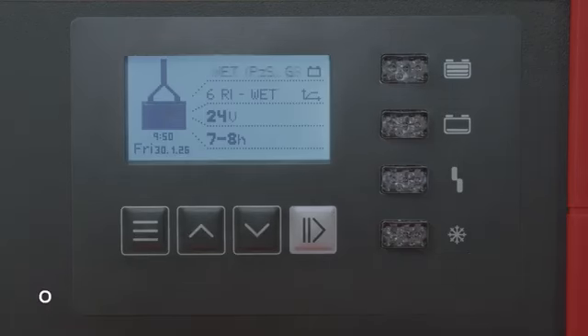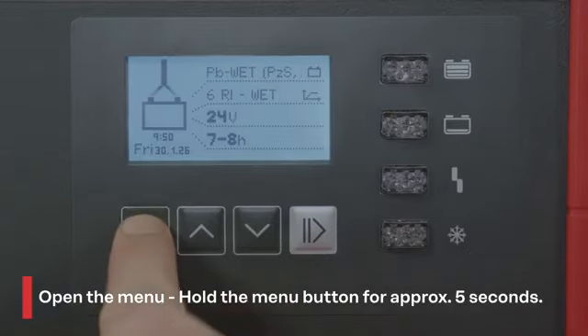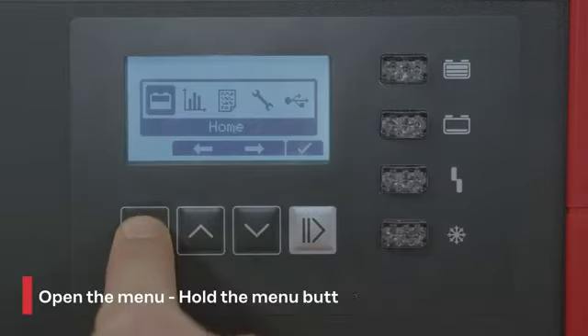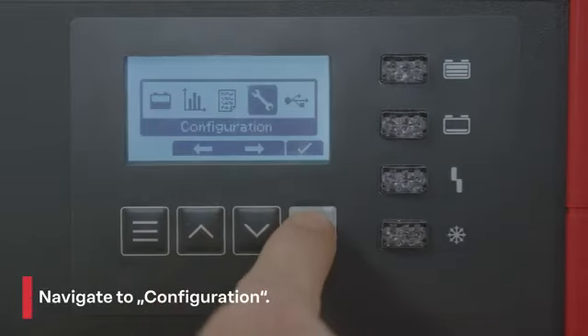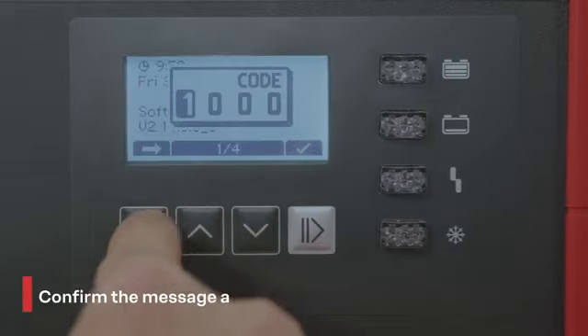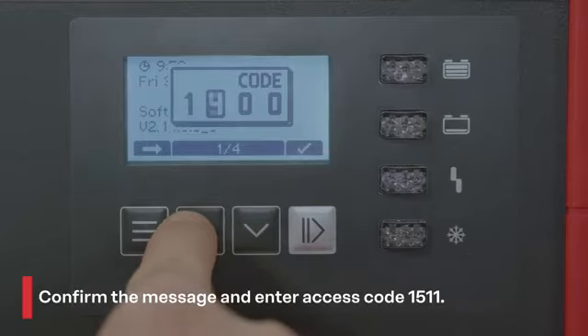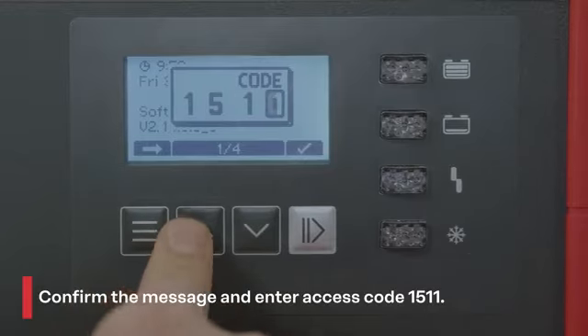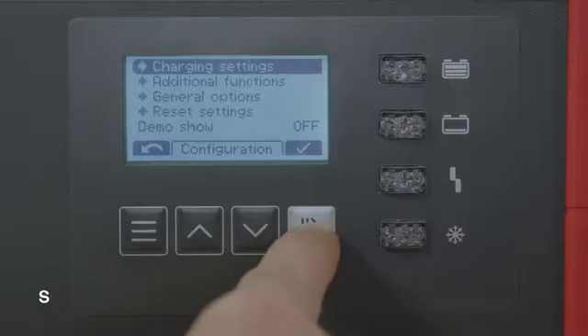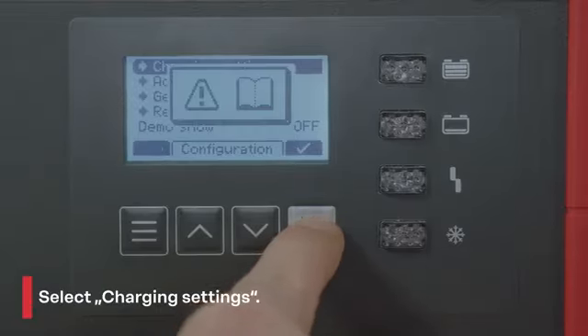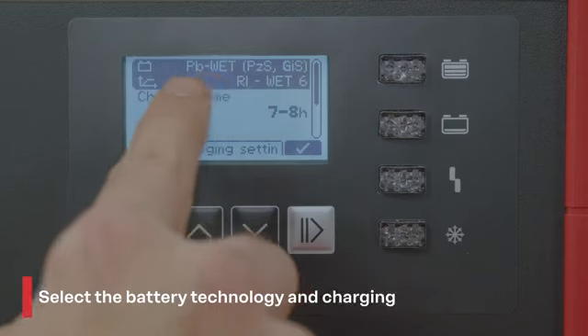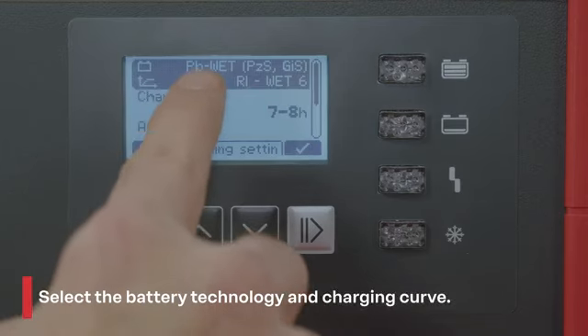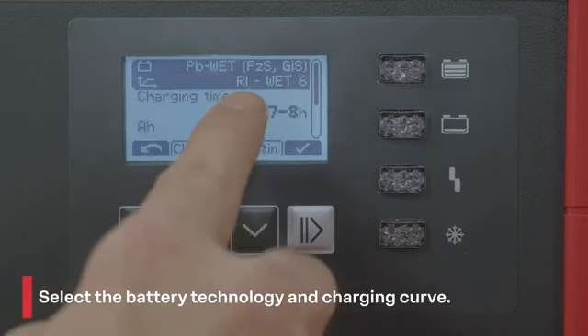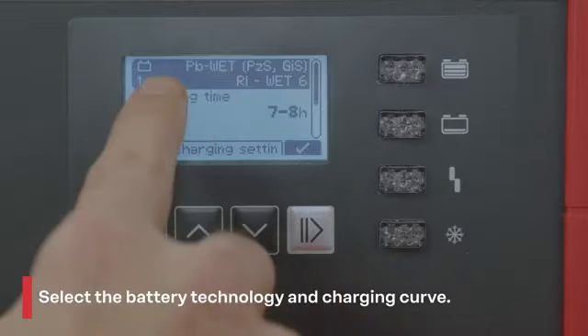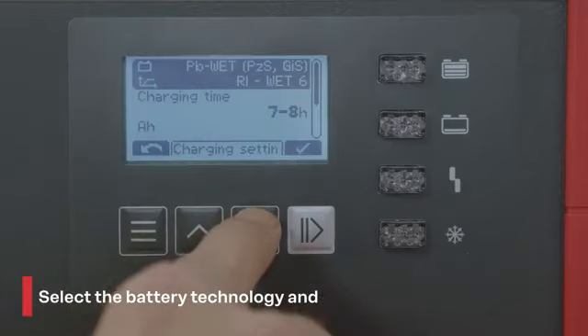So first we will enter the menu. We press the menu button for 5 seconds. We are selecting configurations and we enter the code 1511. We are selecting the charging settings. Now we have already selected our battery technology and our charging characteristics. In our case it's Pb-WET and the RI charging process.